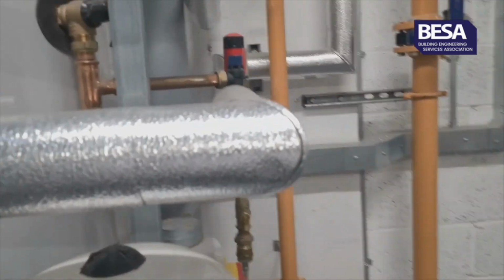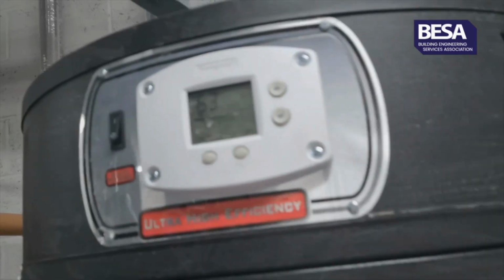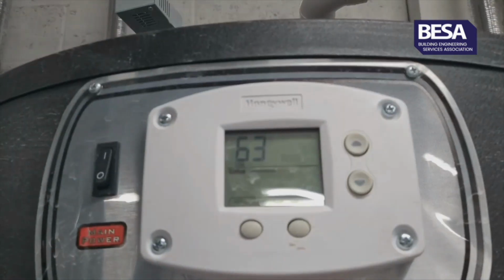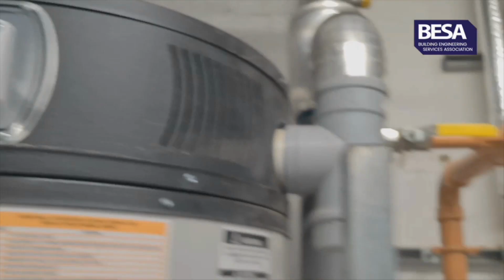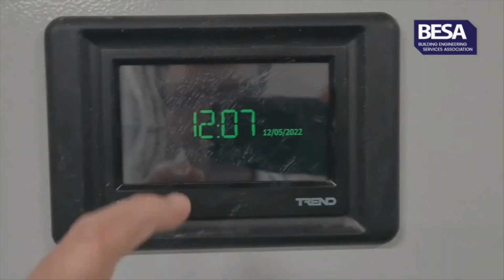Sorry, that's not actually cold feed, that's actually HWS return from the buffers. I'll go through that in a bit more detail in a minute. So the temperatures on these have been set, as you can see there, they're all set to 63 degrees, and we do have a building management system on this job, an IQ View 4 controller.